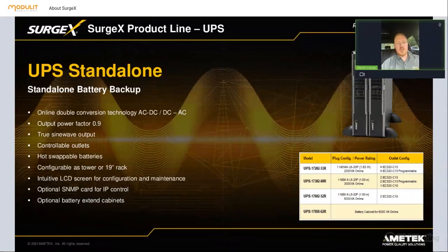Our UPSs have very good power factors. This UPS offers a 0.9 power factor, meaning you put in 1,000 volt amperes and get 900 watts out. A lot of units on the market only offer 5, 6, maybe 700 watts, but you're anyway paying for the 1,000 volt amps at your net supplier, so ours are very efficient.